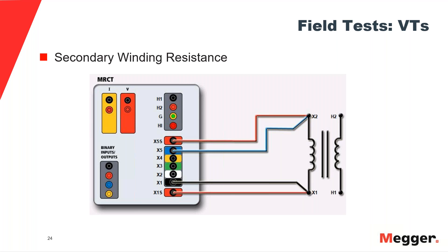Secondary winding resistance: we want to make sure the circuit is still intact, with no shorted turns, no high-resistance connections from the terminals of the VT all the way to the control section of the circuit. We also use that resistance value for modeling the VT. The method involves connecting to the secondary side, injecting a DC current, and measuring the resulting voltage drop to calculate the resistance.